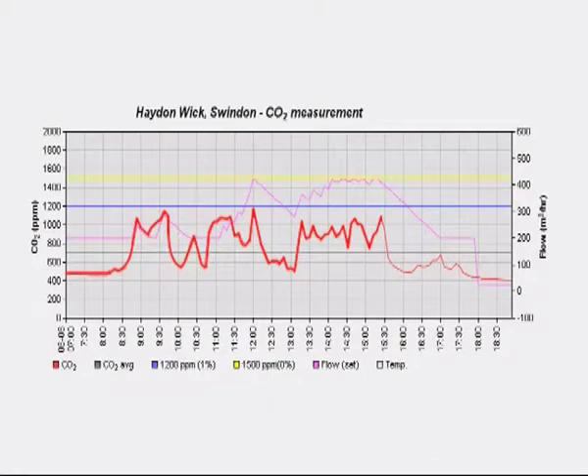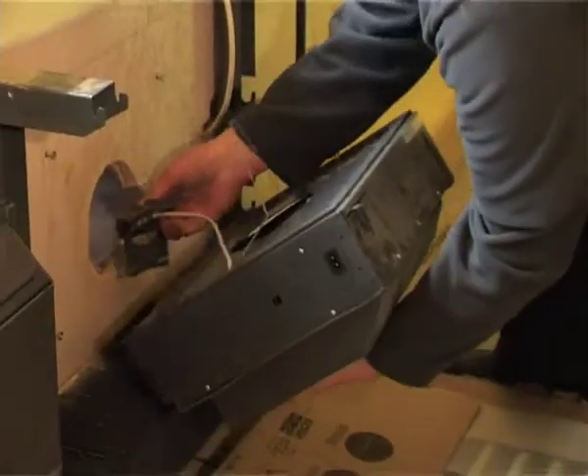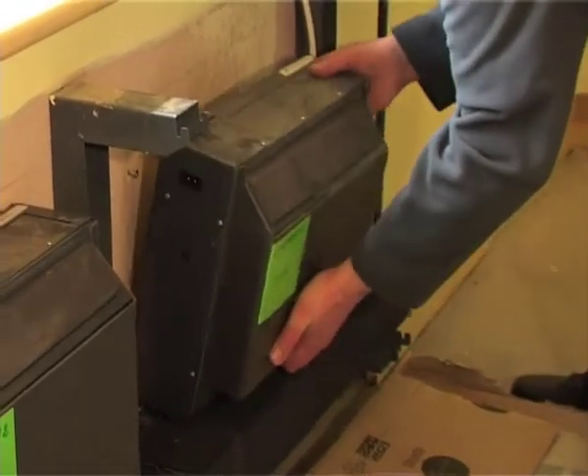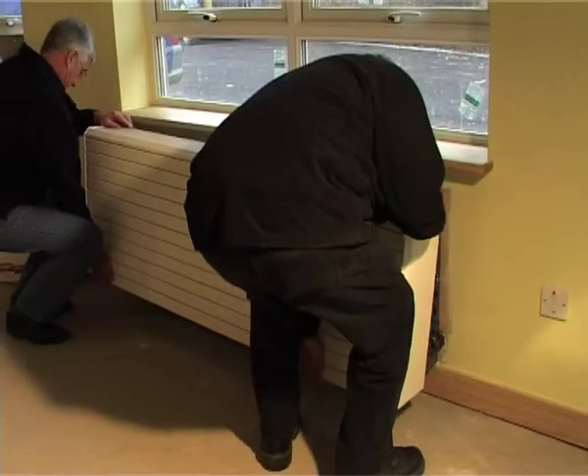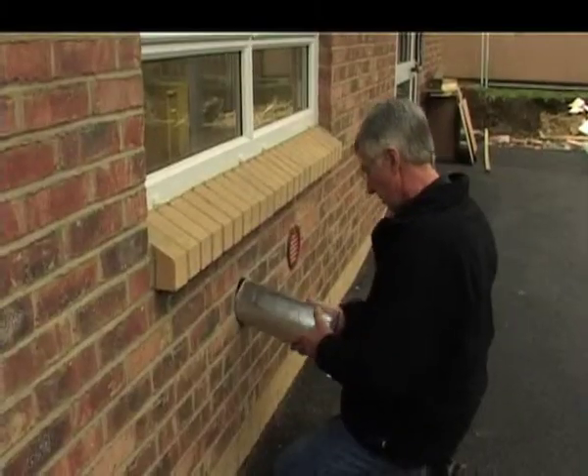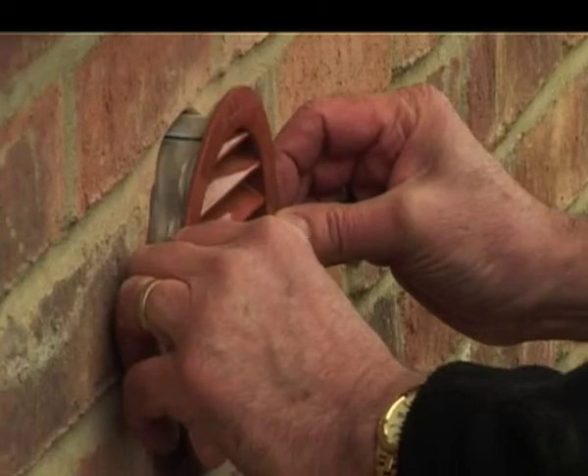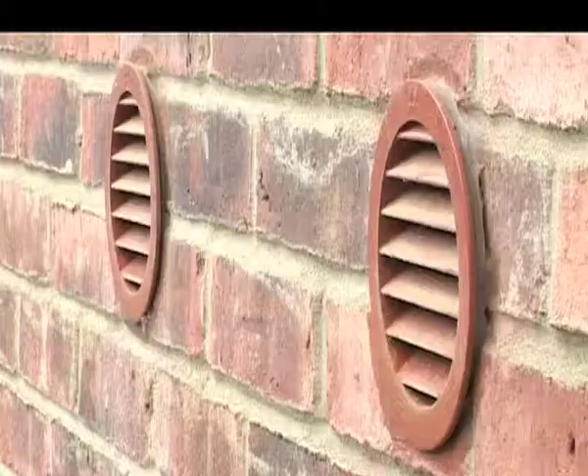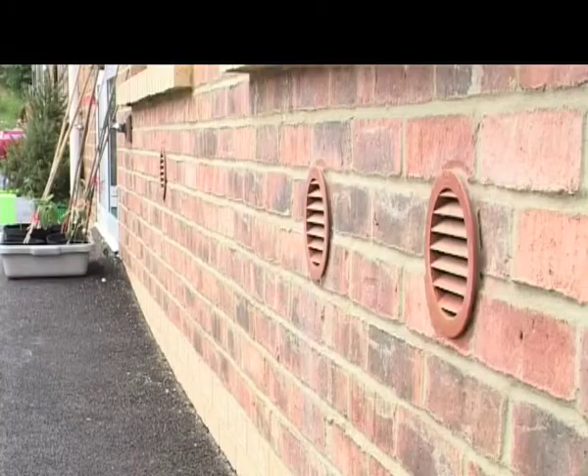The systems also offer considerable energy and cost savings to the school. Low H2O radiators alone will cut energy consumption by around 10%. When used in conjunction with a balanced oxygen air refreshment system, certificated independent testing in Holland has demonstrated that by limiting air changes to the volume of air necessary to maintain air quality, less heating output is required, and this saving rises to around 20% compared to uncontrolled natural ventilation.